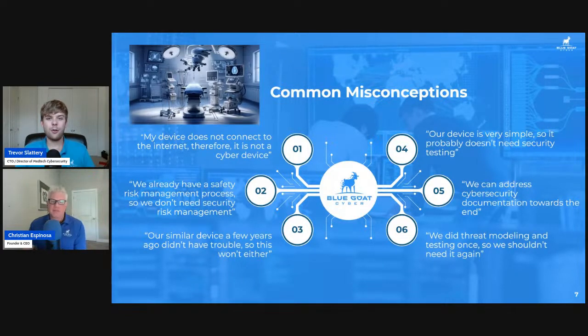We identified a vulnerability in the device where, when it read that pad, we could decide how many uses that pad had left, and we could set it to any arbitrary number we wanted. So we could reuse these single-use pads 10,000 times, and they would very quickly become non-sterile. If a patient were to do that, or if a hacker were to manipulate a pad to be reused and a patient wasn't warned to replace it, they might get very, very sick. So even if it's a very simple device, there can be a lot that goes wrong.